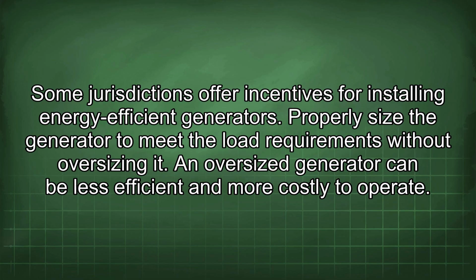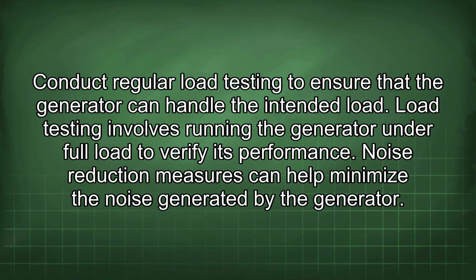Properly size the generator to meet the load requirements without oversizing it. An oversized generator can be less efficient and more costly to operate. Conduct regular load testing to ensure that the generator can handle the intended load. Load testing involves running the generator under full load to verify its performance.